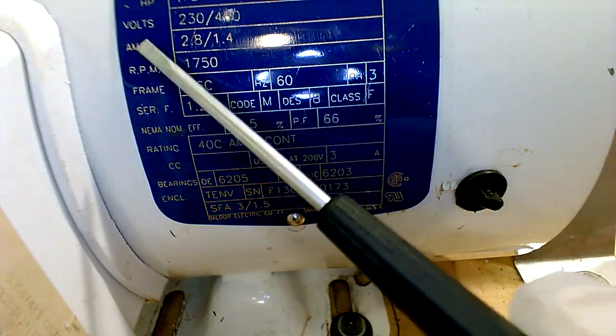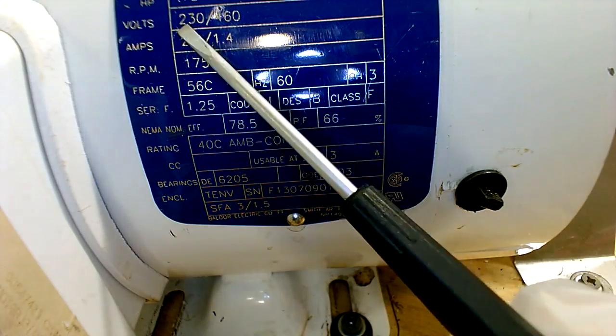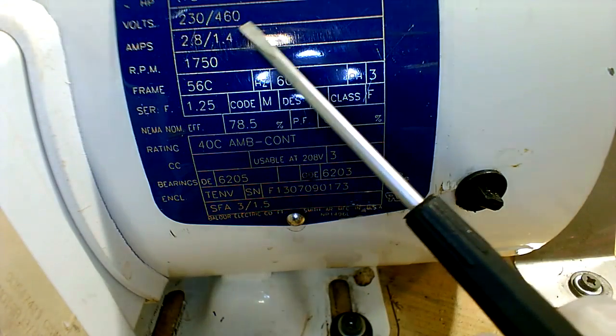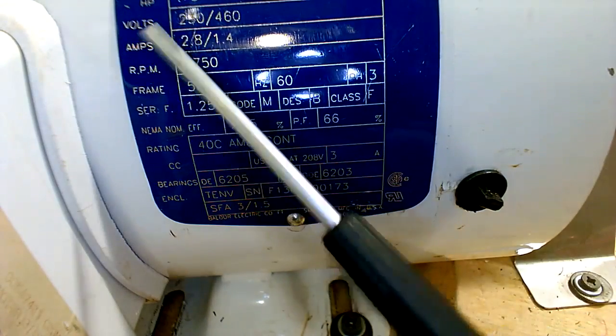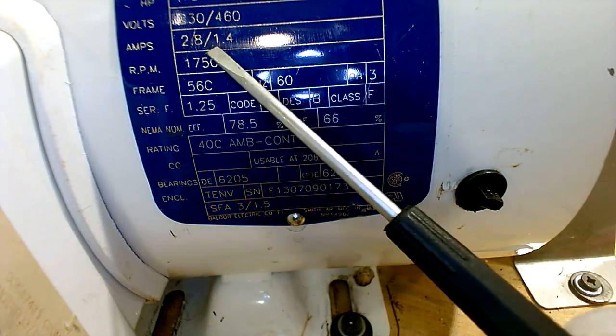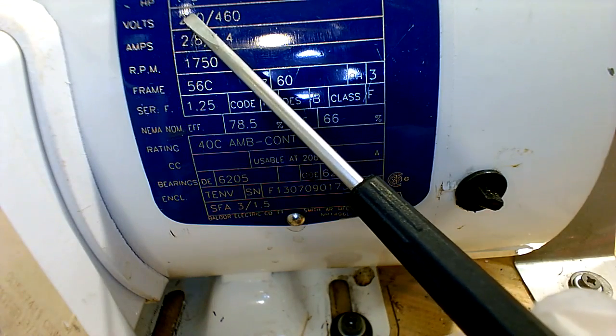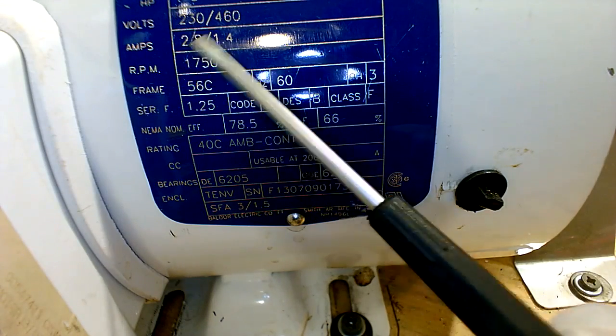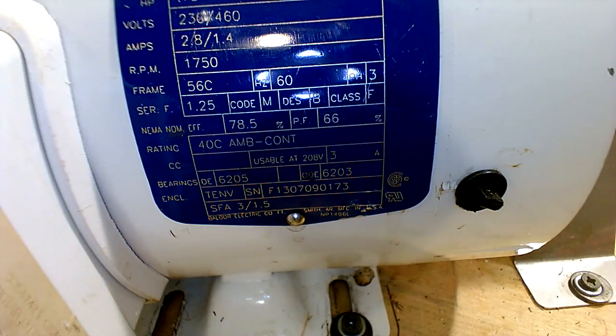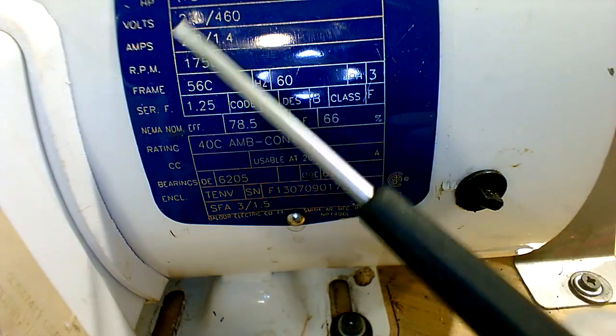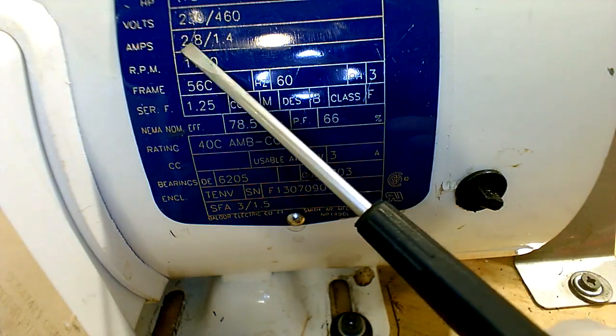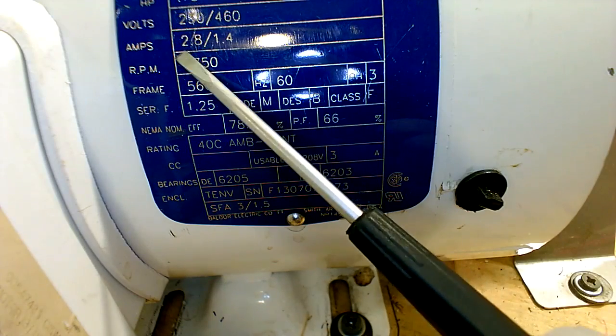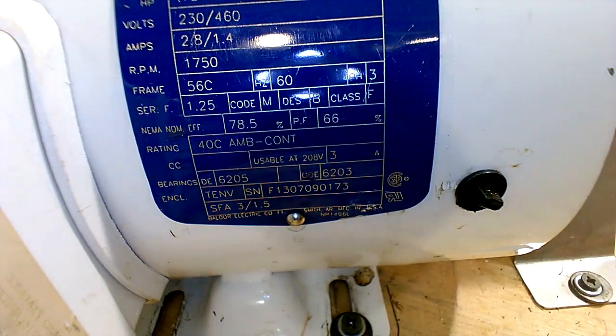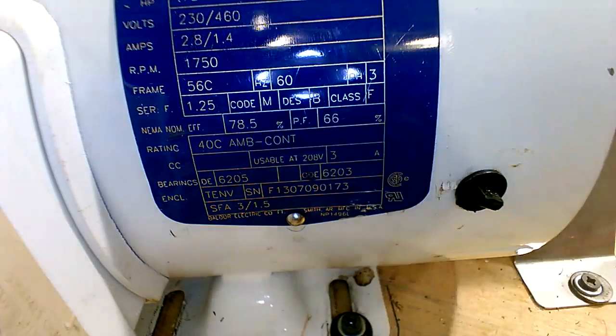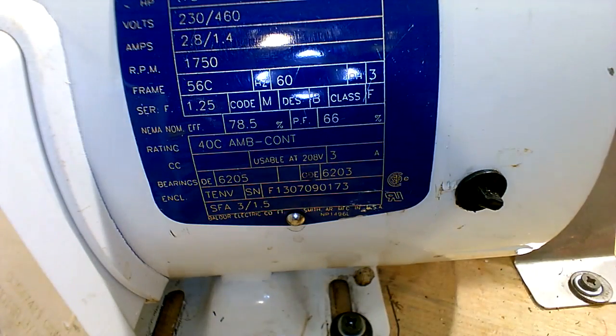You see right here, for voltage, the low is 230, the high is 460. So look right here, Brandon. For amps, there are two amp readings: 2.8 and 1.4. At 230 on the low voltage, you should get somewhere in the range of 2.8 under full load if the motor's actually driving current. It's much less because it doesn't have a mechanical load driving it. Also, a lower voltage is going to change the amps a little bit, but you're not exceeding it. You will have about 1.7 amps. So you're within the nameplate. That's how you know you're within what it should be.